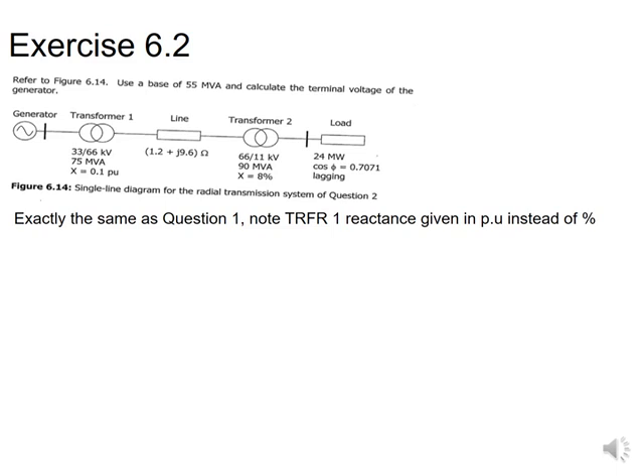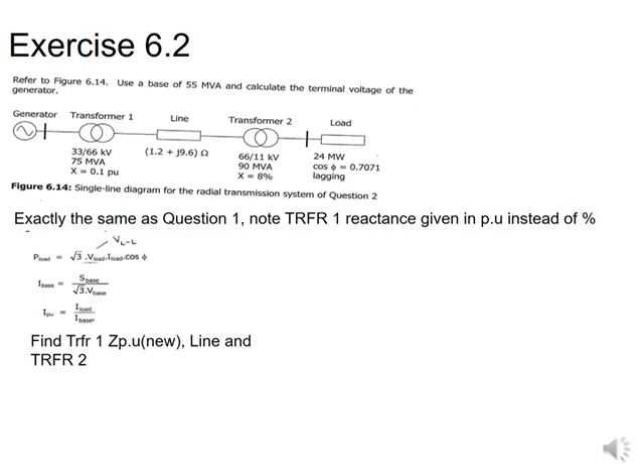Moving to exercise 6.2, you follow the same steps as 6.1. Note the slight difference: for transformer 1, x is given as 0.1 per unit — already in per unit, not percentage. This does not mean you use that 0.1 directly without adjustment. You still start with the load to calculate I load, then I base, and then I per unit. For transformer 1, you take that 0.1 per unit value and multiply by 55 divided by 75.